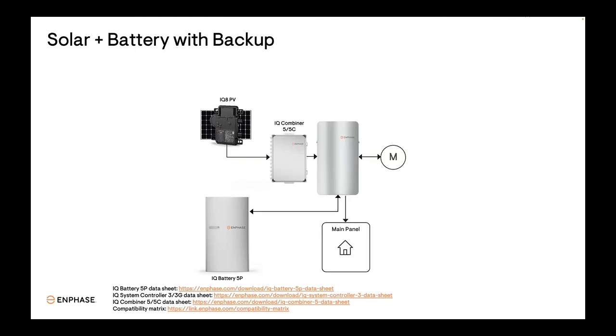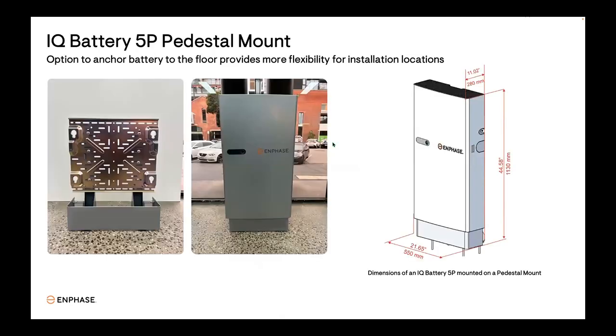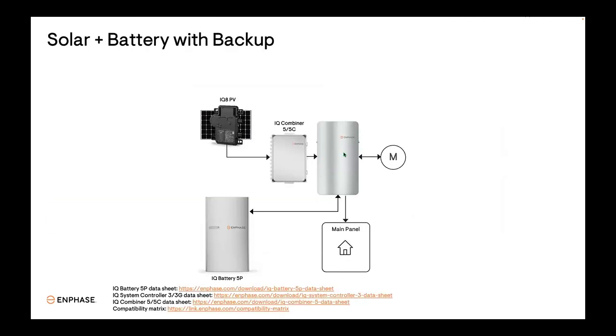That being said, if the customer wants backup power, we have a robust backup solution now with Enphase, with a battery 5P that can start just about any large appliance the customer could throw at it. If it's a backup power system, then a system controller 3 would be required, which is this unit here in the middle—it's unfortunately not labeled for some reason, but that's the controller. Up to 16 of the IQ battery 5P units can be connected directly into the controller. Solar is connected into the IQ combiner, which feeds into the controller as well, and the loads would be connected to the controller also.